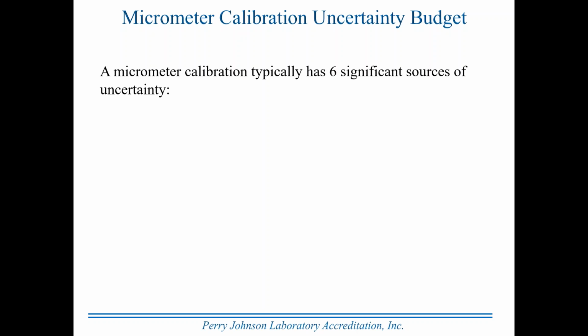But let's proceed. A micrometer calibration typically has 6 significant sources of uncertainty. Now remember, there are many others, but we applied a test for significance and eliminated all but these 6. And the test that we use states that if one contributor by itself, or if several contributors taken together, do not contribute more than 1% of the total, they can be set aside as insignificant. So from that point going forward, we would only evaluate the 6 remaining significant contributors. And we're going to take a look at each one of those and talk a little bit about where it comes from, what causes it, how to evaluate it, how to assign value to it, and then how to process it in an uncertainty budget to ultimately wind up with a number referred to as the expanded uncertainty.